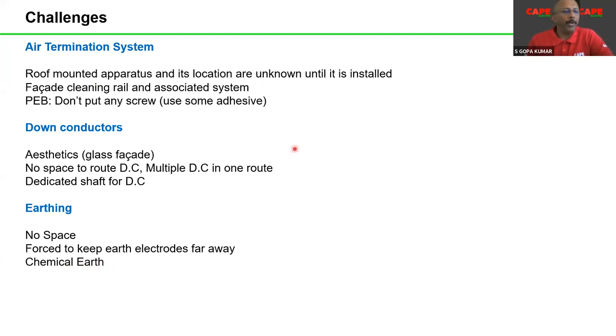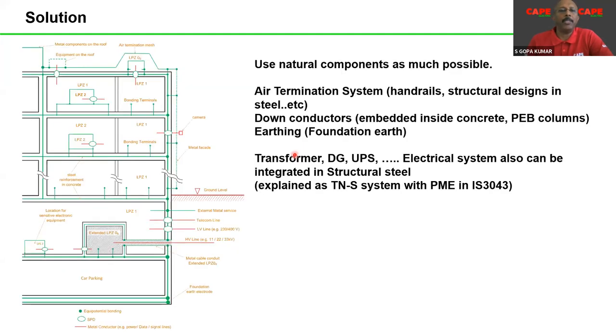So basically, going to the conclusion, what exactly is required is that the best solution can be made by using natural components, especially for high-rise buildings or large industrial buildings. Use natural components as much as possible. For example, in the air termination system, on the parapet, you make a handrail with an MS pipe or a square material. Your handrail will be a permanent structure, and the handrail will work as an air termination system. You must interconnect the handrail with the structural steel, something like this. The handrail must be connected. So use the handrail, which is an efficient way.